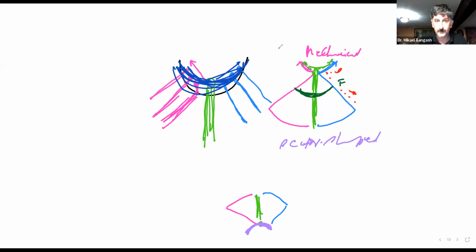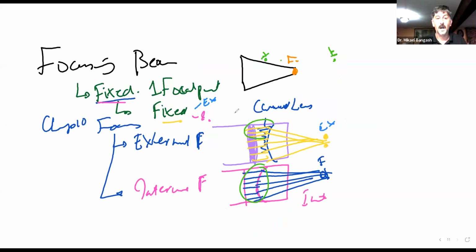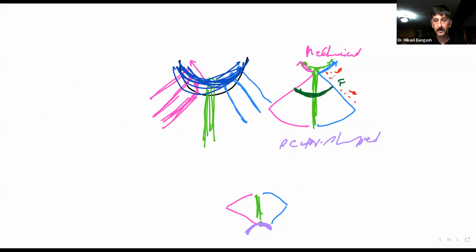I have a question. So you said you can't focus at a shallowest depth? That's not what I said. Okay, if this was your focal point here, it is fixed, due to the hardware of your transducer, the way that it is made. Since it is a fixed focal point, you can't shift your focal point to a shallower depth, neither can you transfer it to a deeper depth.